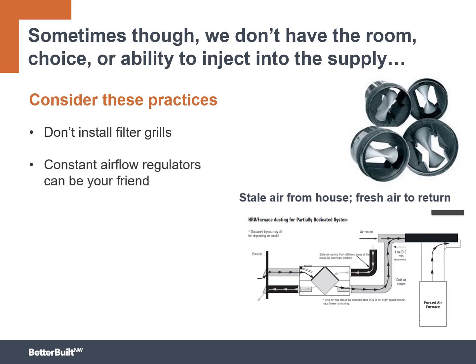So if you can help it, don't install filter grills if you are going to integrate your HRV into the return side. Second, you can use a product called a constant airflow regulator. If you look at the upper right-hand corner, those are CARs, or constant airflow regulators. And there's a couple of different models and brands out there. This one uses a bladder that actually inflates as pressure builds up around it. So the velocity of air starts going through faster. It creates pressure. That little bladder in there inflates a little bit. And what a constant airflow regulator will do is kind of insist that you don't go beyond a maximum amount of flow. There are other types which are kind of gravity dampers that work similarly. A constant airflow regulator is a pretty good way to make sure that the lower the pressure, the easier it is for air to move through it. But when you get a high negative pressure in that return, it will not oversuck more than the designed amount.